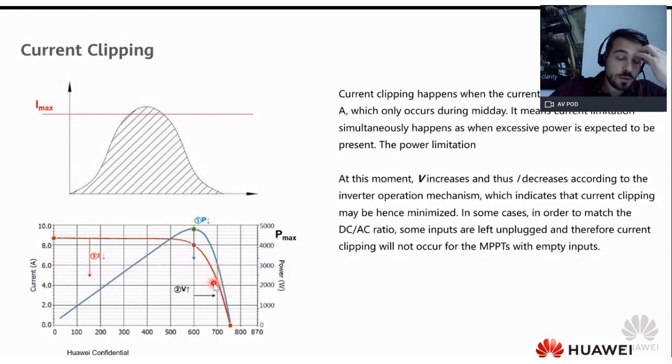This can actually also be checked in the monitoring portal, not at this moment, but in 1 or 2 hours, if there is a lot of sun, no cloudy conditions, and the inverter is operating at full power, so full AC power is coming. You might see that the voltage is increasing, and voltage usually increases when the temperature is dropping.